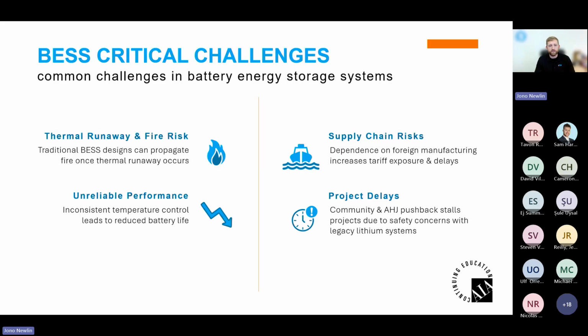That's not necessarily related to these others, though it is a key factor that really impacts critical challenges within BESS. And then the project delays - this one maybe some of you deal with predominantly - but you see community and AHJ pushback. They could stall projects due to safety concerns with some of these lithium systems. You find this in places such as California, in New York. There's moratoriums put in place by fire marshals because of community pushback, where they don't want to deploy any battery energy storage systems until there's better standards put in place for their specific locality. There are projects that have been AHJ approved for large-scale energy storage, and the community has shut it down in a vote, and now the developer couldn't launch that. So the project delays are directly linked to thermal runaway and fire risk.